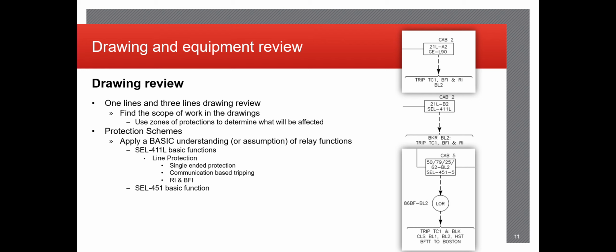Reclose initiate is extremely beneficial in some cases where if there's a quick little fault on the line that may self-mitigate, or you get a bad reading for a millisecond on the line, it can open and close the breaker in an instant without losing too many customers, in a sense. The breaker failure initiate is the same idea when we talked about the lockout relay previously. Pretty much is the worst case scenario tripping function that triggers a lockout to open up all the necessary equipment.